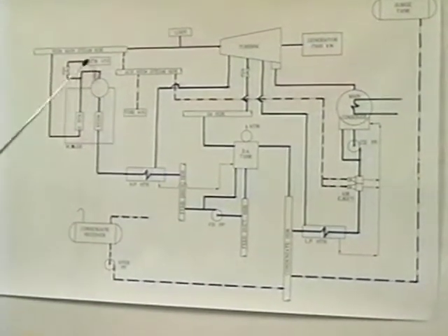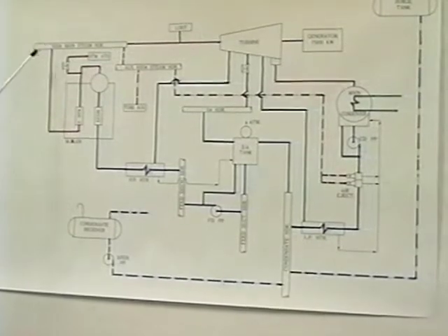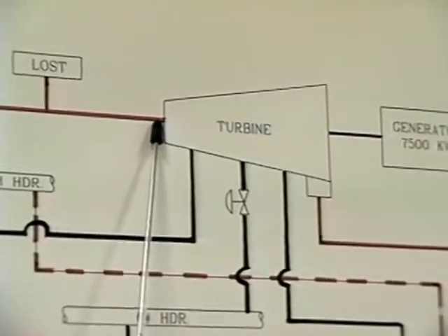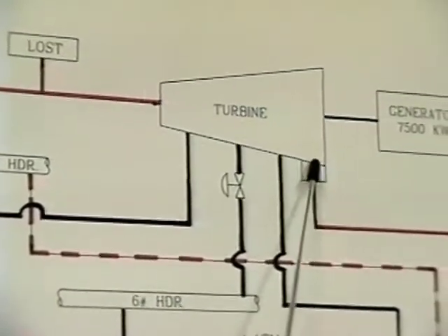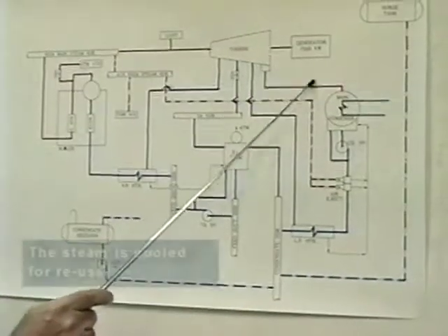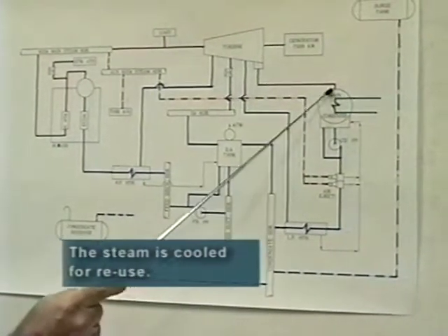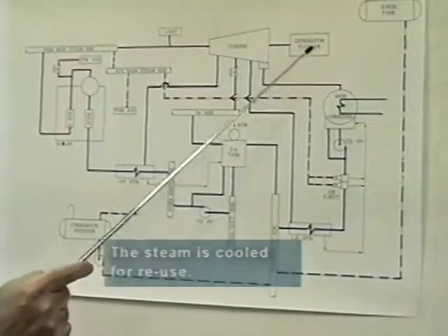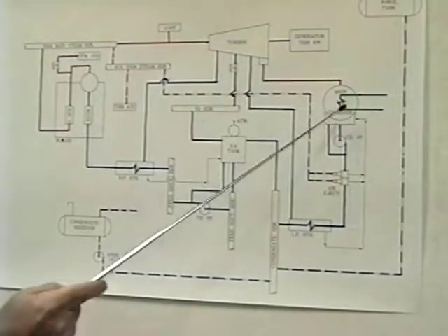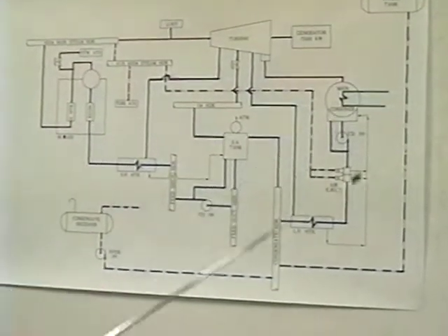The steam that comes out of the superheater is about 825 degrees. The steam enters the turbine at around 825 degrees and exits the turbine at around 110, 120 degrees. The steam is then led through a condenser, which is cooled to condense the steam back to water, which is then reused in the cycle.